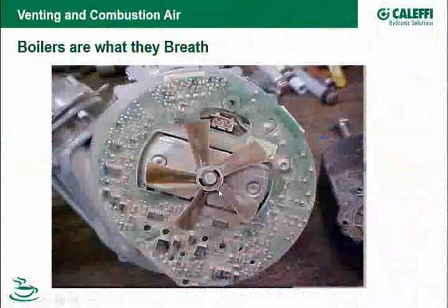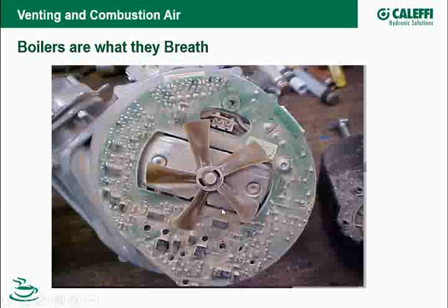Boilers are what they breathe. This was a sealed combustion boiler, believe it or not. So all the intake air was coming from outside, and the exhaust was going outside. It was vented, both the intake air and the discharge air. But they were sheetrocking in the house, and this is all the dust that had sucked in through the louvers on the side of the cabinet.